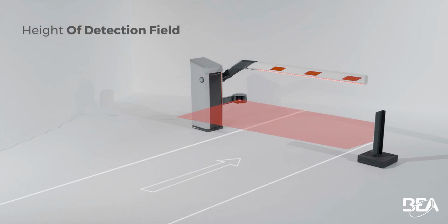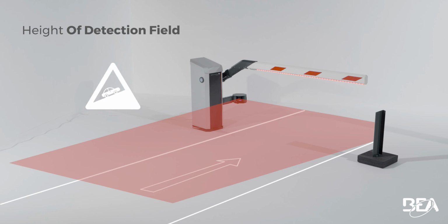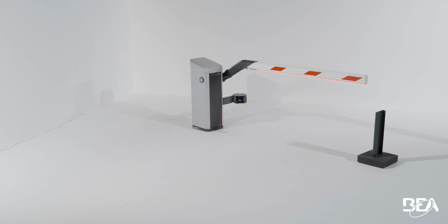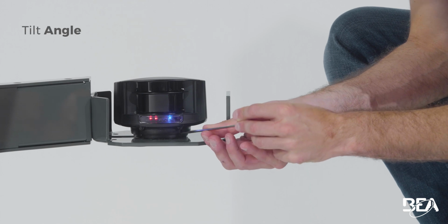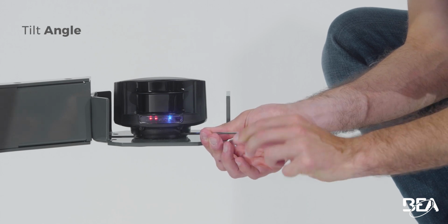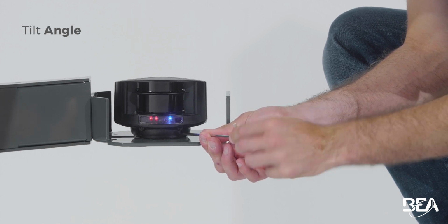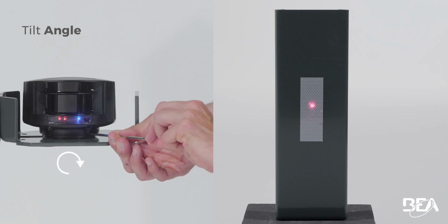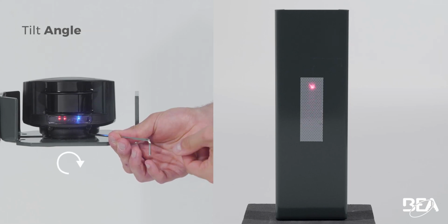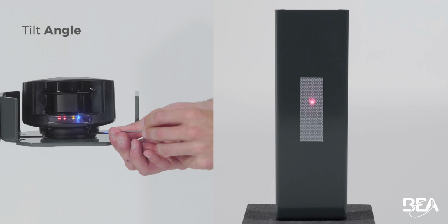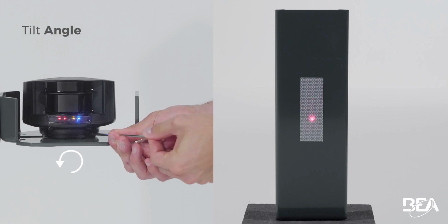It is important that the detection field is parallel to the road level. Particularly pay attention if the road is sloped. If necessary, adjust the tilt angle of the sensor using a hex key. Turn it clockwise to tilt the beam up. Turn it counterclockwise to tilt the beam down.